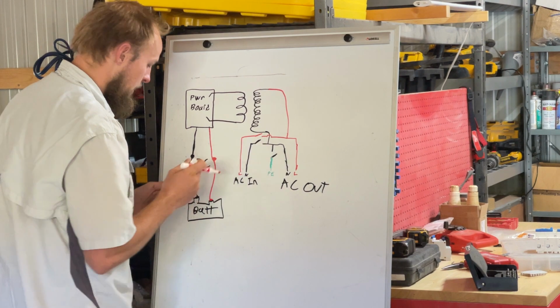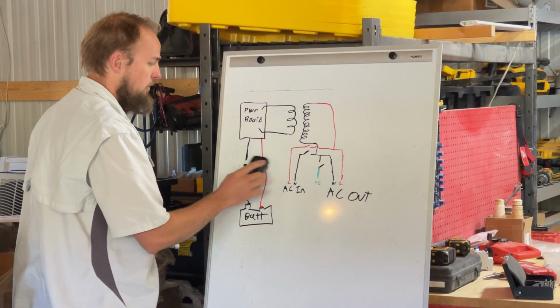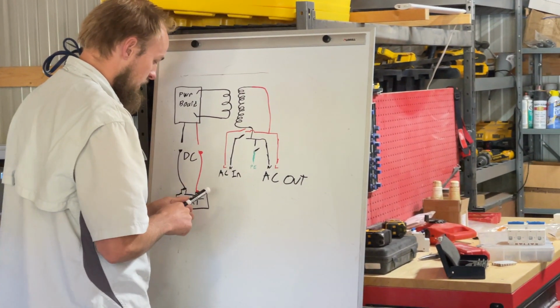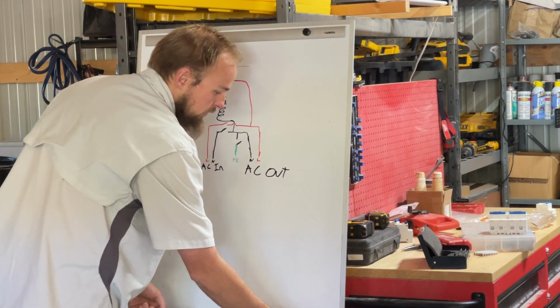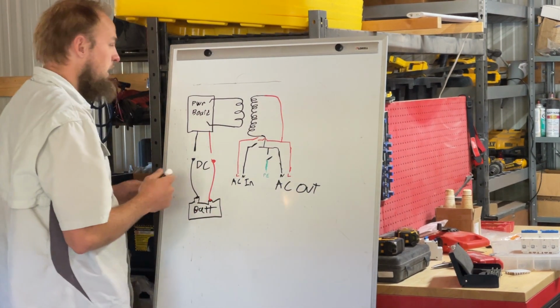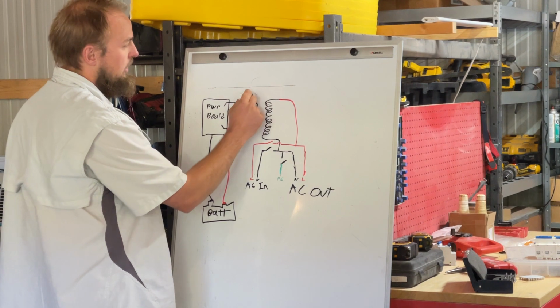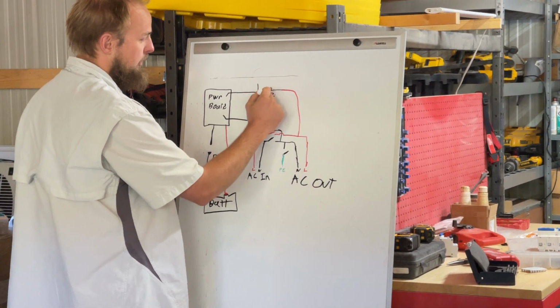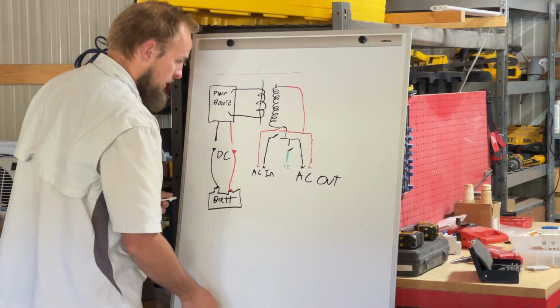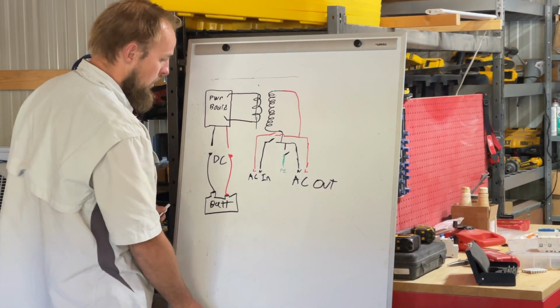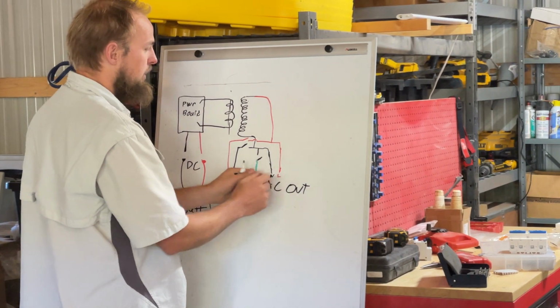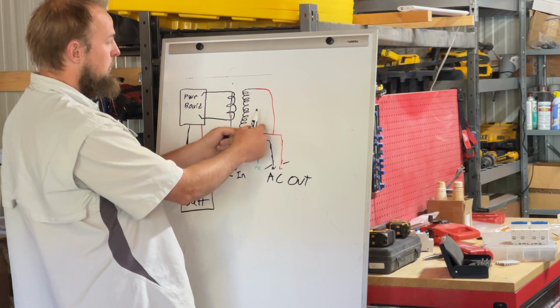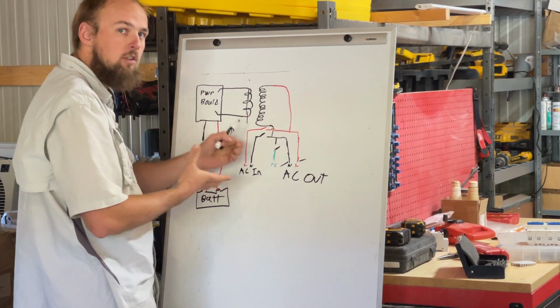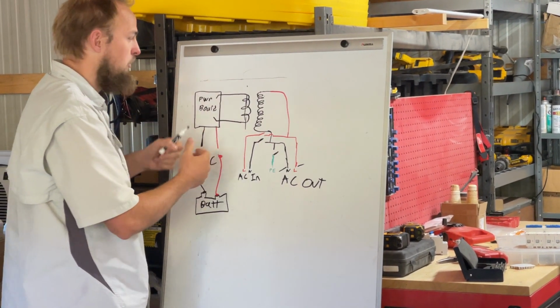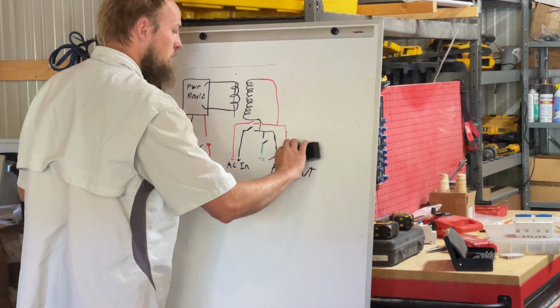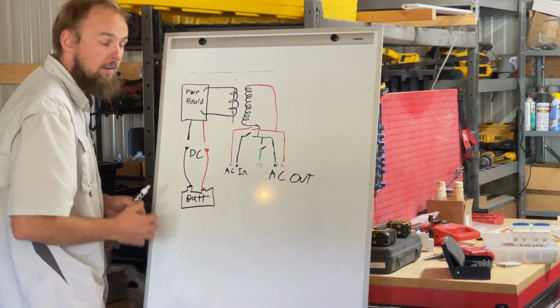So if your power is off, if your inverter is turned off, then that's disconnected. Now there's no AC in the system. It's important to know the way the transformer works before we go into the next thing. When you apply the AC voltage to this side, it's creating this magnetic field, which is then creating the magnetic field over here, which is then creating this voltage. And so when it's all turned off and there's no magnetic fields, all this is a coil of wire. And so if you put your continuity tester between line and neutral, there will be continuity because it's just that free coil of wire. There's no voltages being pushed anywhere, no magnetic fields blocking the flow of current. So it's perfectly normal to have continuity between neutral and line when the inverter is turned off.